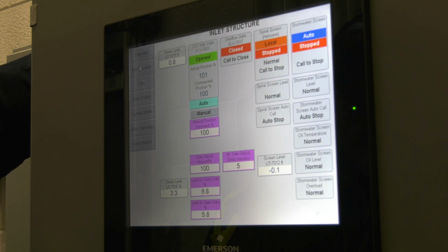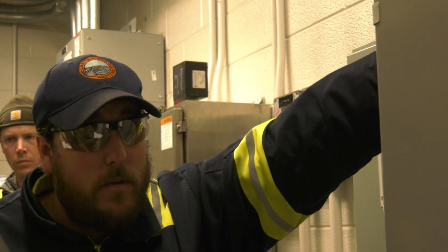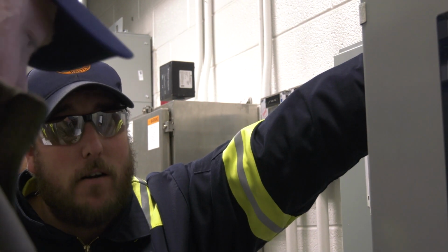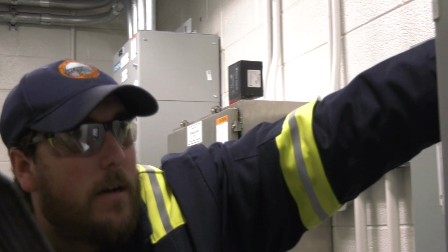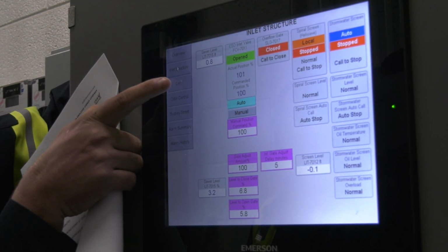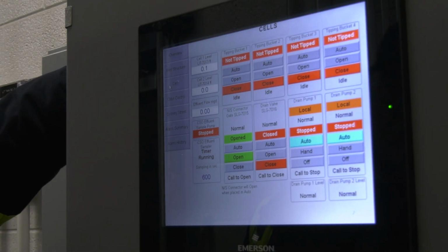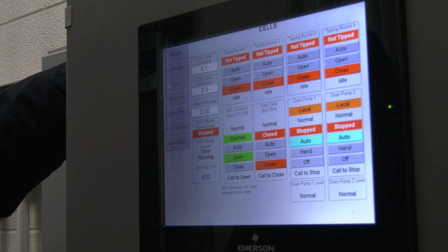So we don't really have any control. It's based off of floats down there. Right now, the way we do it is when the CSO is completely full, your level is going to be right around 10 foot. Then we'll open up the drain valve. That'll drain it down to 3 feet. And once it's drained down to 3 feet, that's when you use the pumps to pump the rest of it out. Okay, so it's 3 foot now to 2.67. Yeah. Okay, that made a change then. All right, and you put the drain pumps in auto down there to control them. Drain pump starts, stops, got that. Simulate low flow, did that.